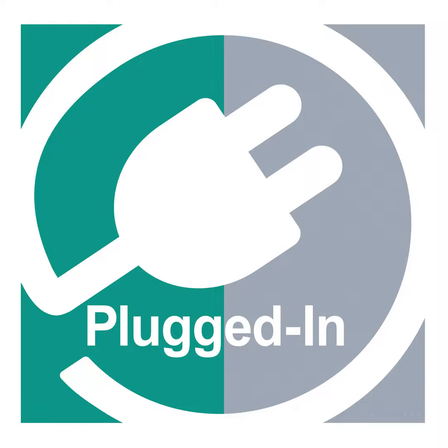So you can run your machine via IO Link without needing to access the IO Link Master at all. Just use the infrared interface, hook it up to the sensor on the outside. The connection between sensor and IO Link Master is not disturbed at all, and you can read all the values.